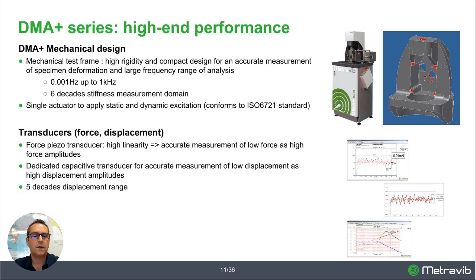So this high rigidity test frame implies a very large frequency range in terms of testing capability. Because the resonance of the frame is much higher than 1 kilohertz, the usable frequency range can be much larger than, let's say, classical DMA. Another consequence of this design is the large measurement range in terms of stiffness variation. This test frame makes it possible to follow the variation of stiffness of a specimen over up to 6 decades.